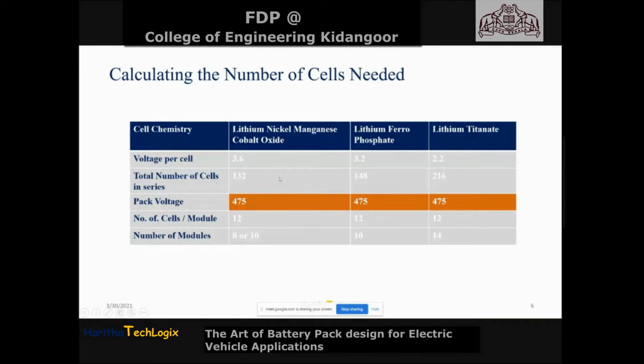And the total number of cells in series might differ. For example, if it is a 475 volt pack, how many cells do I need to connect in series? We can calculate it from here - it is approximately 132 cells we need to connect in series to achieve this particular pack voltage level. If it is LFP, the number of cells needed in series might be more, because the voltage per cell is lesser.